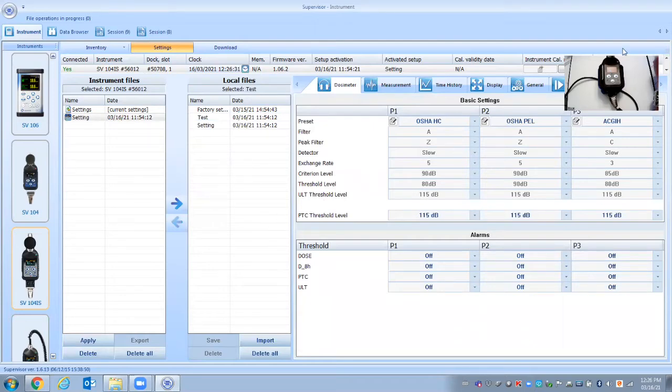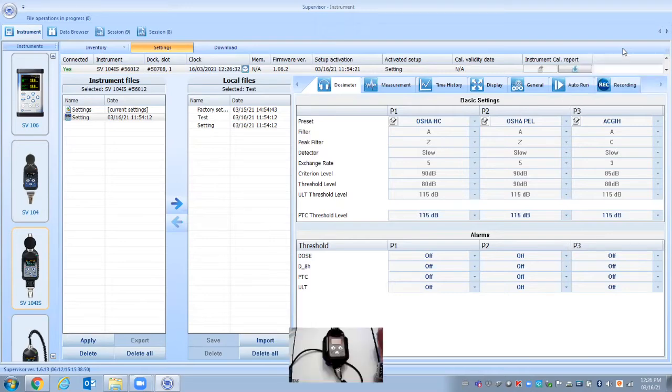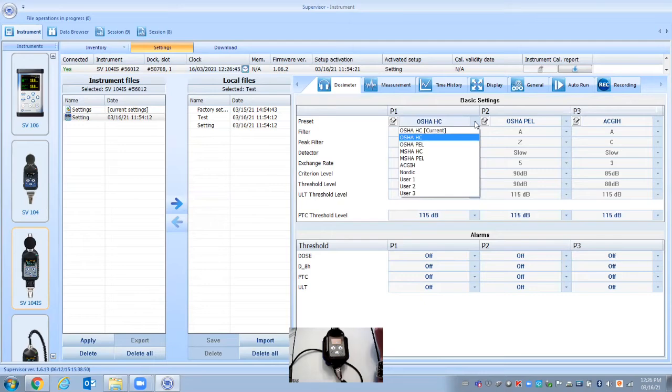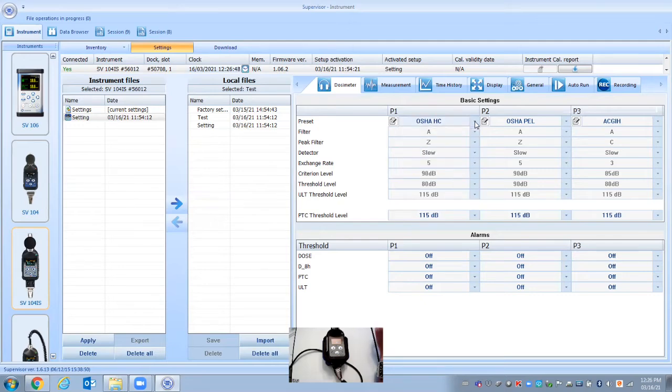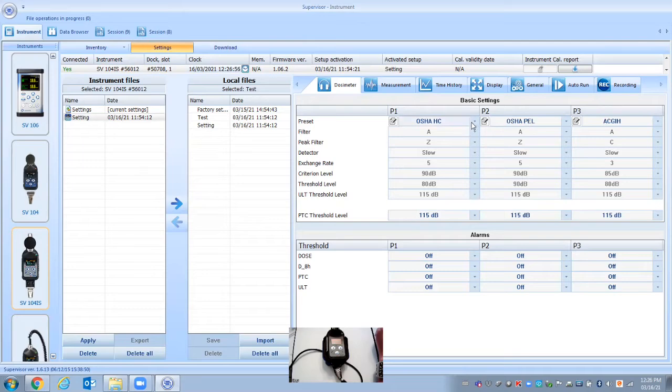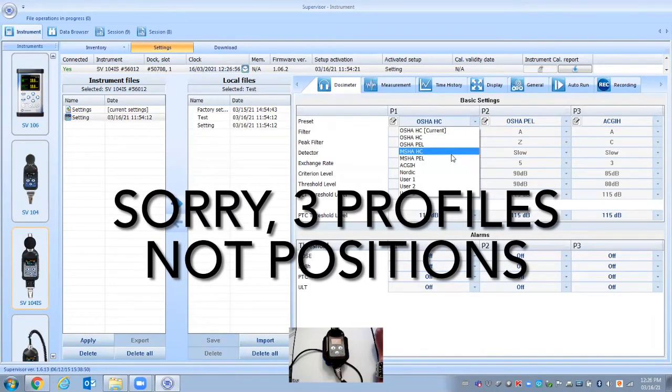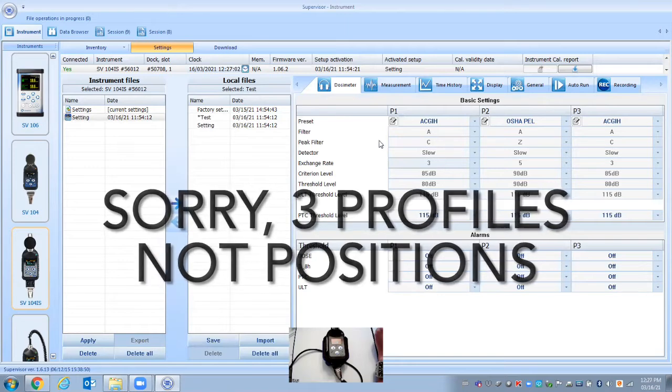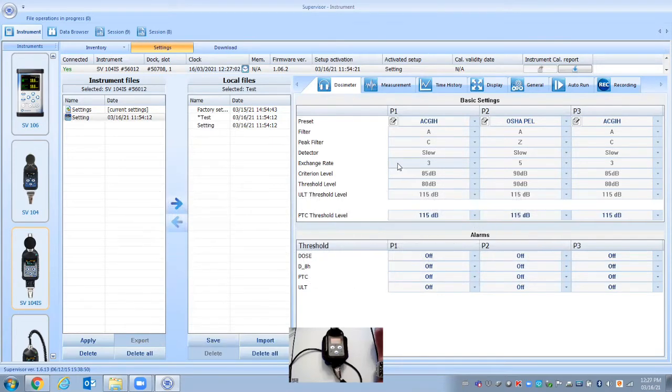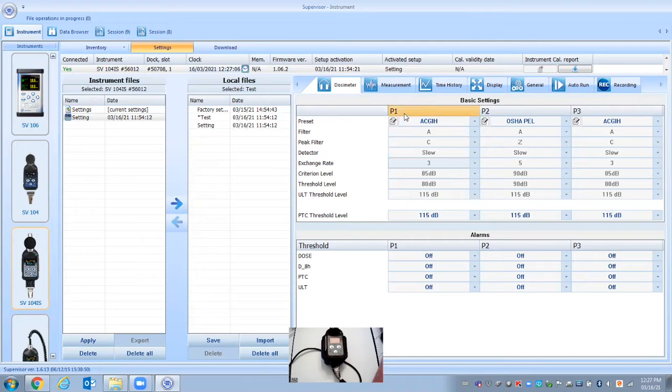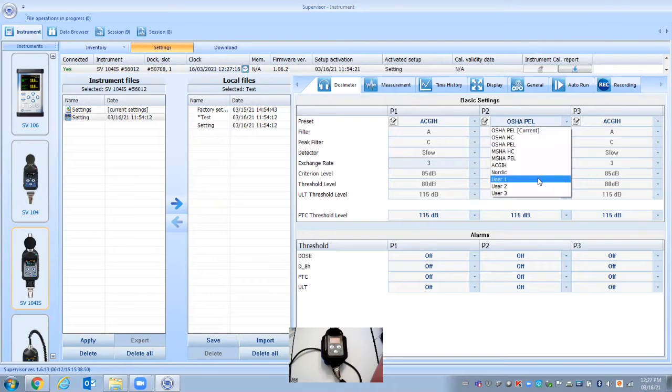Now, you can see that from the factory, they ship it with these default settings. So if you're in other countries, you actually have lots of different choices here, but I'm located in Canada. And the main setting we use is ACGIH, which is in the third profile. This is like having three separate dosimeters in one. But I really like that with this pull down, I can select profile one, which most of the results are reported as you're going through the recording. It favors profile one or set up one. So I'm going to move that to profile one. And these other two don't really matter.